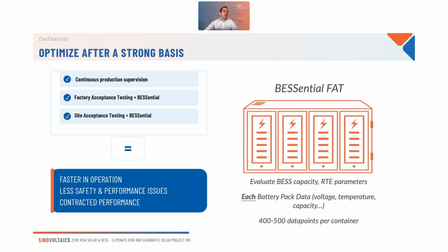Using these three pillars of quality checks and inspections, you will get your system faster into operation, since you eliminate most of the issues—be it a small baby issue or a real performance issue—found during the inspections. Especially with this BESSential analysis, when you can verify that not just the container level but also the racks and modules are working as they should, then you can really say that you have the contracted performance of the system.